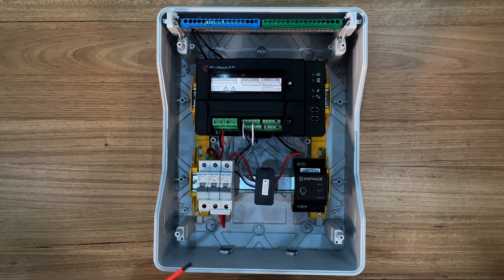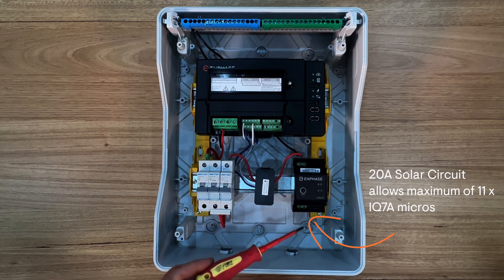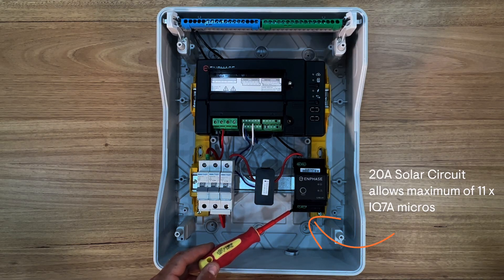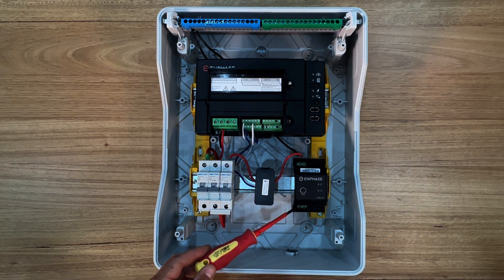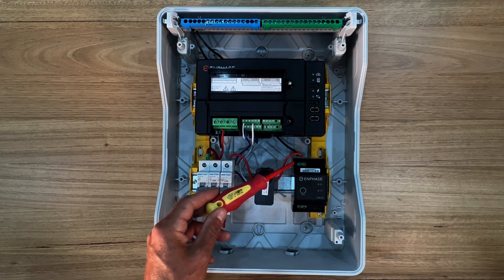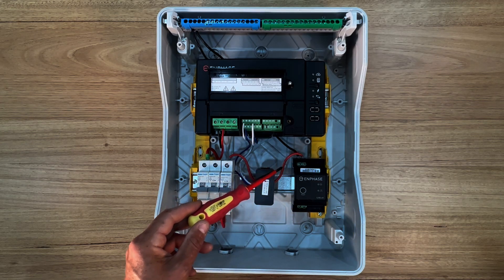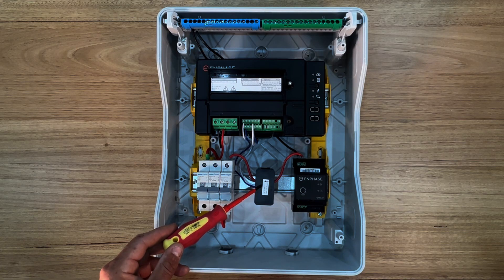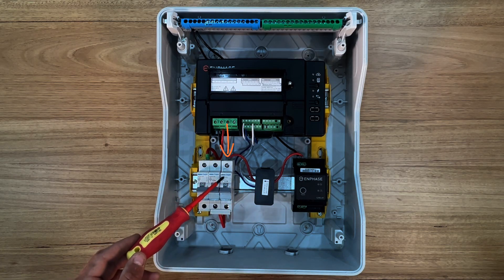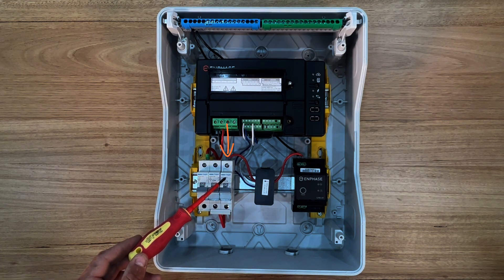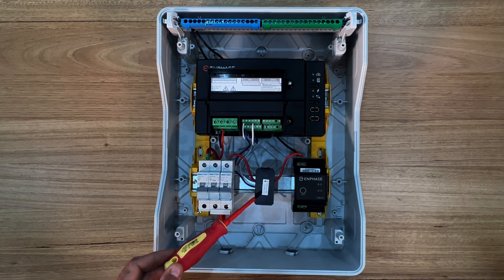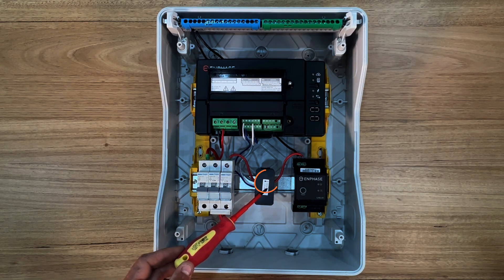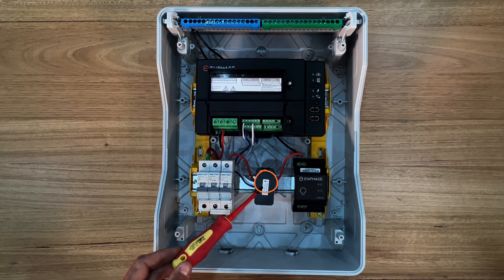A 20 amp solar circuit is wired to the side labelled from PV on the single phase Q relay. The active conductor of the solar circuit passes through the current transformer and connects into the 20 amp circuit breaker. Note that the arrow of the CT points away from the solar and back towards the circuit breaker.